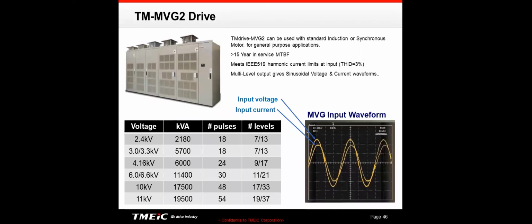Now, this was a technology, I tend to call it the Robicon technology. Robicon popularized this in the United States and patented it, although TMEIC was actually making these before Robicon was. But a lot of people think of this as the Robicon technology. Basically, you use a transformer with lots of secondary windings, and you use low voltage converters and inverters and put them in series in order to generate your output waveform. Again, TMEIC has this technology as well. And you can see down here at the various voltages, the number of pulses and the number of levels.